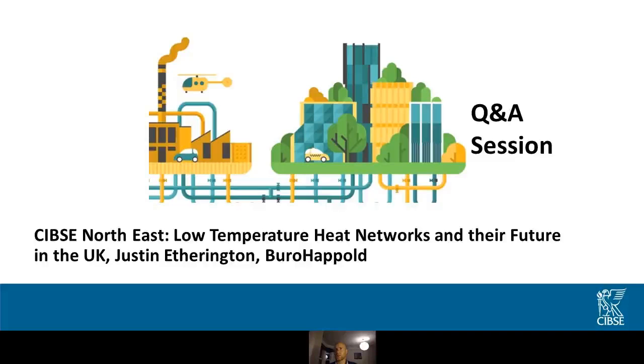Flow temperature doesn't drive the flow rates. With lower flow temperature transitions, you need to consider the mass flow rates involved. That's why moving to a lower temperature system often needs energy efficiency measures to reduce the demand of the space. As you reduce the output you get from a radiator with a lower flow temperature, you can match that with reduced demand.